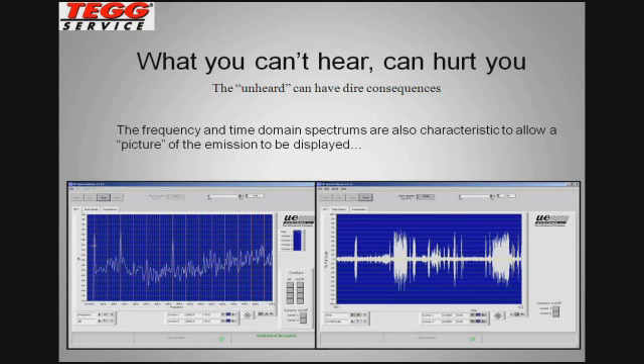We traditionally see 2 or 3 of these harmonics as what's called false frequencies, or spikes in the frequency spectrum, and in between each of those peaks, or 60 hertz cursors, there's a lot of activity going on, or frequency content. That's indicative of an electrical type problem where you have a high amount of frequency content. This particular frequency domain can be confused with other electrical problems that to us audibly sound very different. So to use just the FFT as a standalone tool would be a mistake, in my opinion.